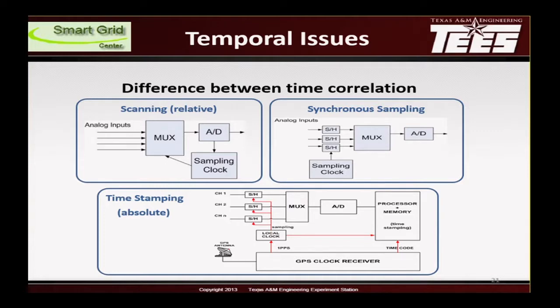The other thing is the time code, the actual absolute time from these receivers, which may be used for time stamping. That means I can put a stamp on a signal at the source and correlate it to absolute time. This is very important when merging data from multiple IEDs. For example, in synchrophasor systems, when we move data from synchrophasor units across the system into the data concentrator, it's very important to know which sample comes when, and whether they are all arriving at the time they should be.